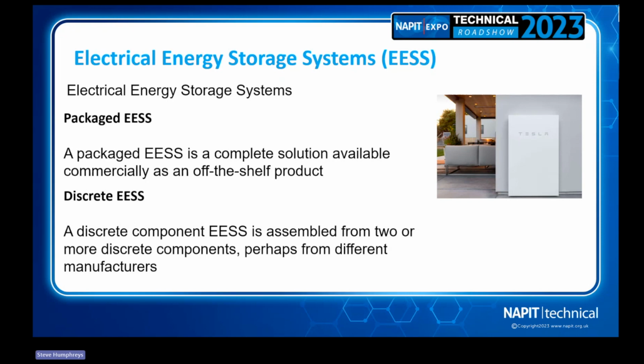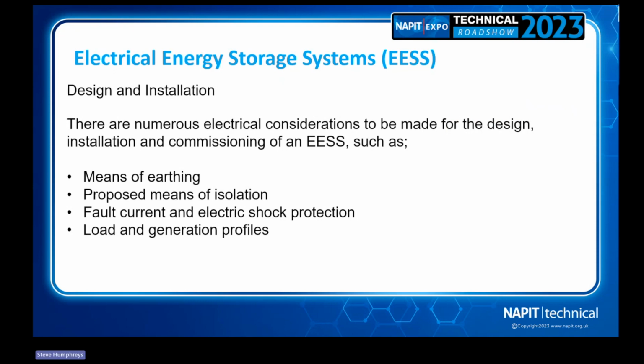Fit to manufacturer's instructions in conjunction with BS 7671, whereas your discrete component one needs a little bit more of the designer to check that things work with each other. So is it compatible with those component parts? Lots to consider for the design and installation, especially when in island mode. What is the means of earthing? Have we got the troublesome PME system there that gives us loads of grief with everything we install? What are our proposed means of isolation? How are we providing fault protection and additional protection if needed? And what does the customer actually want with this? What do they want it for? Do they need it as a backup supply in island mode, or do they just want to save on their bills and charge the battery in the day, not bothered what happens overnight, don't want to feed back to the grid at any time? So you need to speak to your customers about what kind of systems they want.